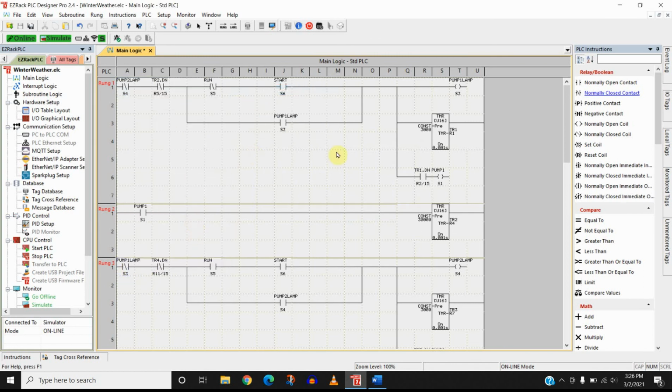So what this does is, let's say that neither one is selected. Either one could be started at that point. Okay, so let's start with the first one here. If run switch is off, I press start. Seal in pump lamp. Pump lamp runs like it's supposed to. If I turn run on after it's been started, this will close down here, but since pump 1 is already running, this won't function. So let's just try it and see. It's easier to watch it than to explain it.